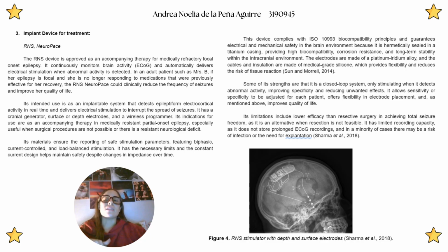Finally, for treatment, I selected the Responsive Neurostimulation System, RNS NeuroPace, an implantable closed-loop device for drug-resistant focal epilepsy. It continuously monitors brain activity through electrocorticography and delivers targeted electrical stimulation when abnormal activity is detected. The system consists of a cranial generator, surface or deep electrodes, and a wireless programmer.